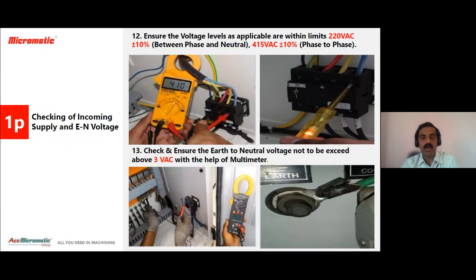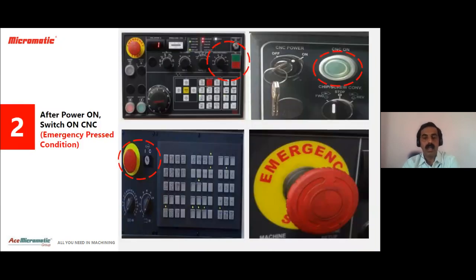Then further, if it is found okay as per the multimeter, then we have to ensure the earth and neutral voltage is 3 volt or below, as per the recommendation from all the FANUC or Siemens, that we have to ensure with the help of a multimeter. If the earth to neutral voltage is more, we have to check the earth pit.